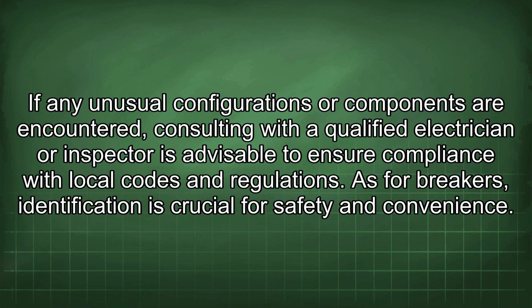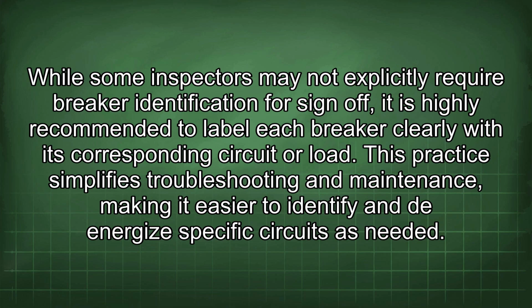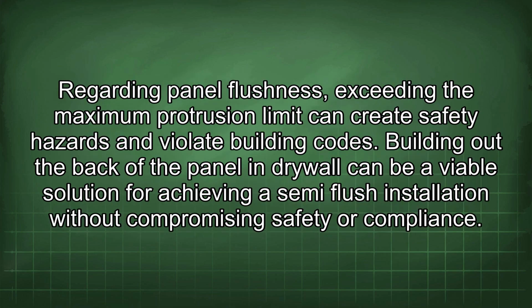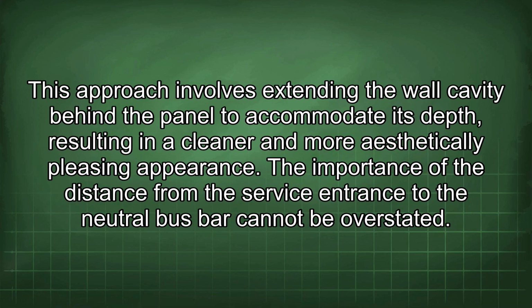As for breakers, identification is crucial for safety and convenience. While some inspectors may not explicitly require breaker identification for sign-off, it is highly recommended to label each breaker clearly with its corresponding circuit or load. This practice simplifies troubleshooting and maintenance, making it easier to identify and de-energize specific circuits as needed. Regarding panel flushness, exceeding the maximum protrusion limit can create safety hazards and violate building codes. Building out the back of the panel in drywall can be a viable solution for achieving a semi-flush installation without compromising safety or compliance. This approach involves extending the wall cavity behind the panel to accommodate its depth, resulting in a cleaner and more aesthetically pleasing appearance.